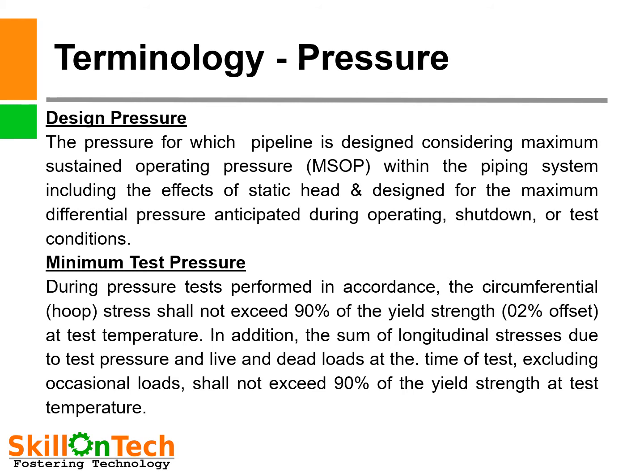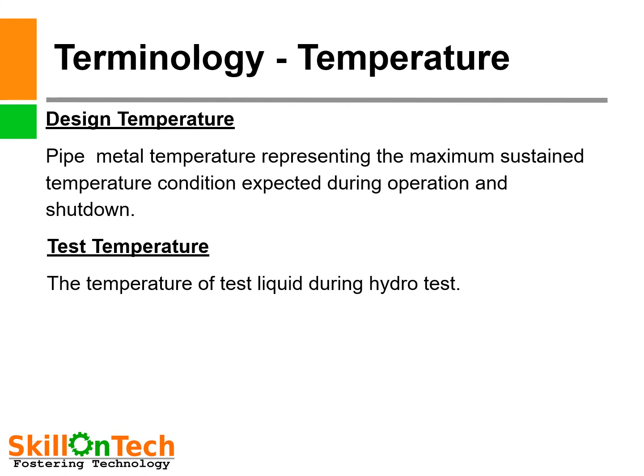In addition, the sum of longitudinal stresses due to test pressure and live and dead loads at the time of test, excluding occasional loads, shall not exceed 90% of the yield strength at test temperature. This strength is of the material. Design temperature is the pipe metal temperature representing the maximum sustained condition of temperature expected during operation. Test temperature is the temperature of the test liquid during hydrotest of the pipeline.